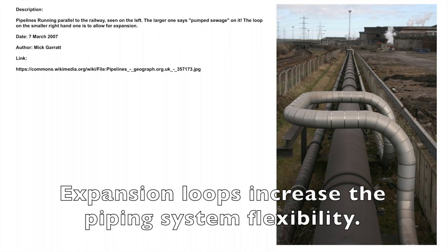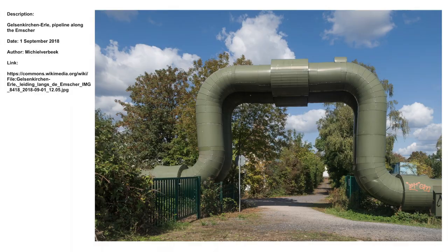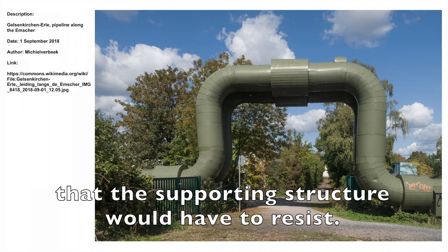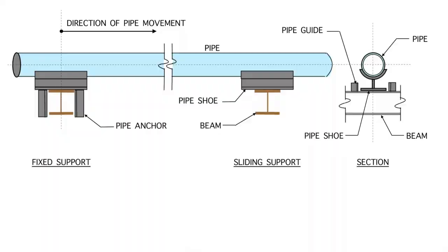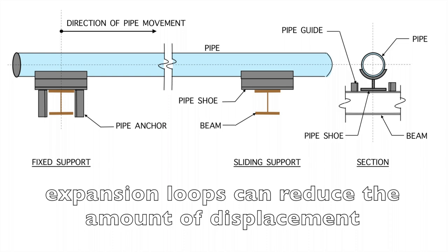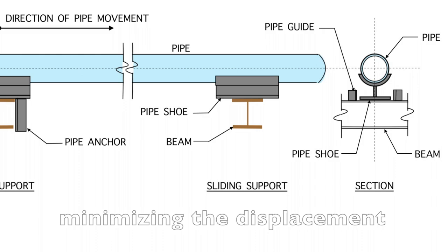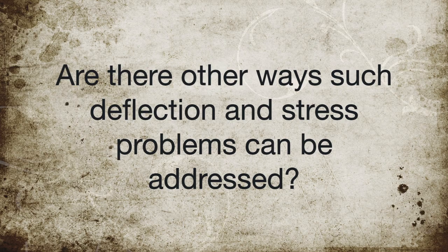One way of addressing this problem is by installing expansion loops. Expansion loops increase the piping system's flexibility — they allow the pipe to deflect within the loops and thus relieve stress. They also reduce the amount of anchor forces that the supporting structure would have to resist. The longer the loop leg, the more flexible and less stressed the system becomes. In the case of pipes with one unrestrained end, expansion loops can reduce the amount of displacement at the sliding end. If the pipe is sitting on a shoe, minimizing the displacement would shorten the required length of the shoe.